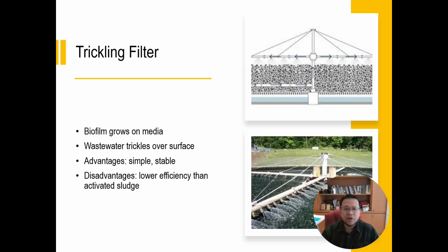The major advantages of the trickling filter are its simplicity and its ability to handle fluctuations in flow, offering stable operation. However, its efficiency in removing BOD is generally lower compared to the fully mixed activated sludge process.